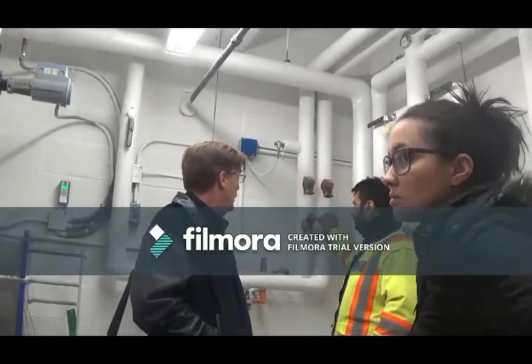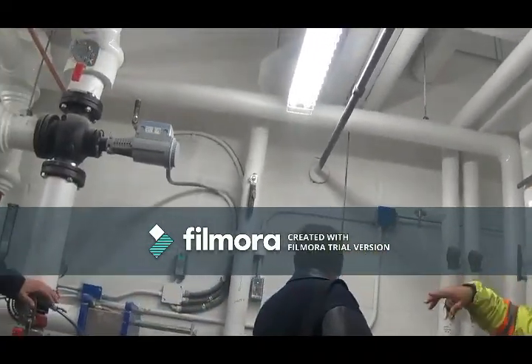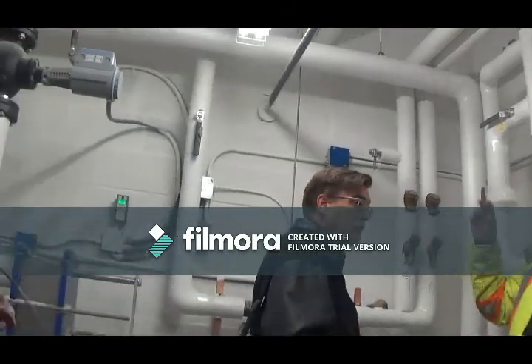I was just checking it. So these are set. Fully open. Locked. And all the ones for all the risers are locked too. So the riser at the end and the riser all the way at the other side are pulling the exact same amount of gallons per minute.